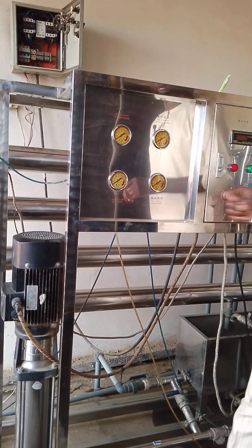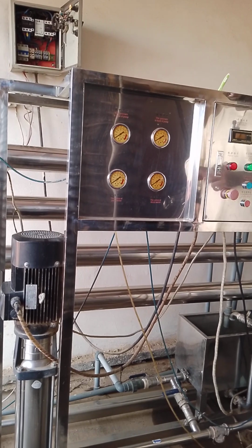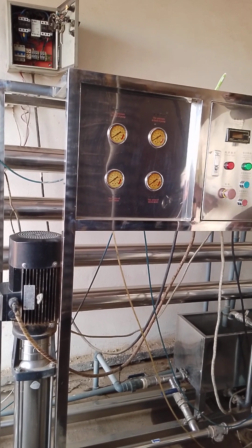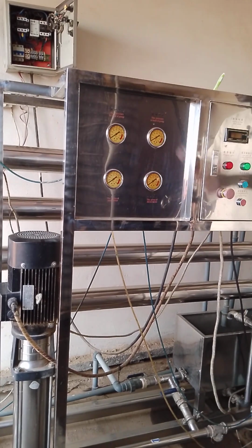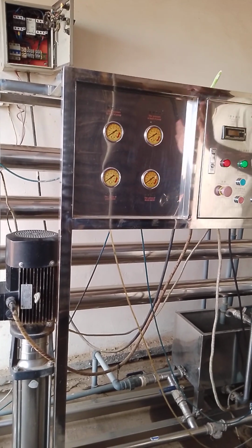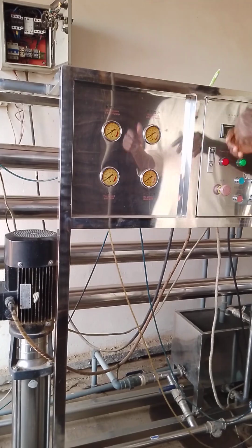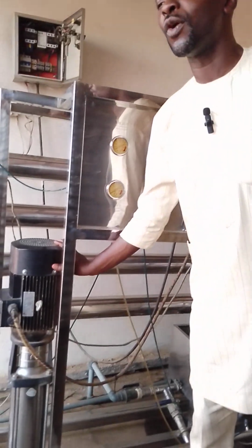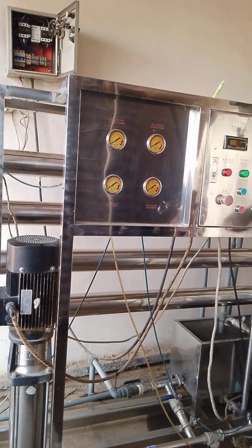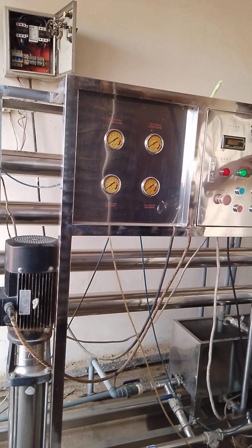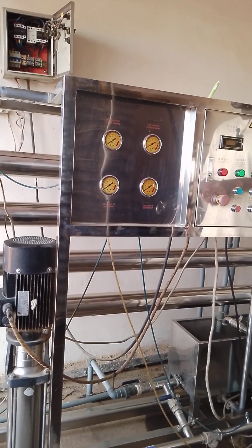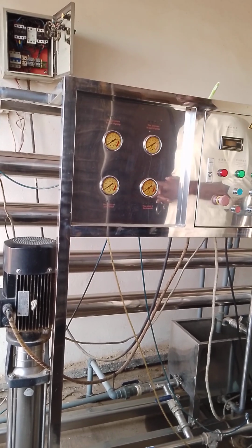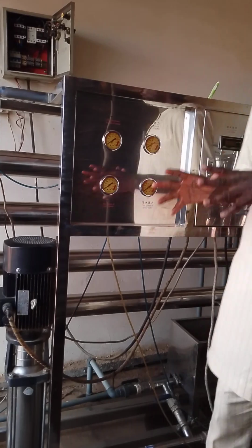Funny enough, some production managers or operational managers are not mindful of this. When they come, they switch on everything, boom, boom, boom, and off they go. They don't even look back because they assume they've pressed the button they need to press and it is working. Unknown to them, they will not go and check whether the water is being transferred to the treated tank. They'll just sit wherever they are, waiting for water to be pumped. In the next 30 minutes, when they go and check, there will not be water in the treated tank.